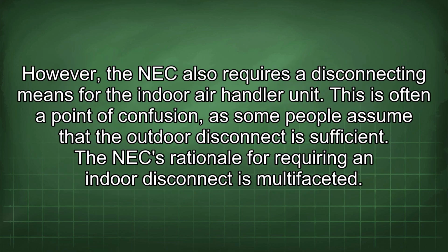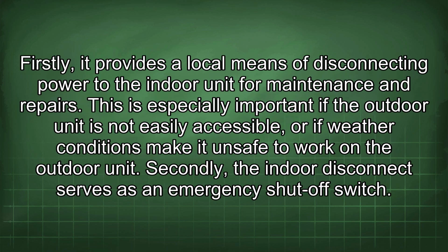However, the NEC also requires a disconnecting means for the indoor air handler unit. This is often a point of confusion, as some people assume that the outdoor disconnect is sufficient. The NEC rationale for requiring an indoor disconnect is multifaceted. Firstly, it provides a local means of disconnecting power to the indoor unit for maintenance and repairs. This is especially important if the outdoor unit is not easily accessible, or if weather conditions make it unsafe to work on the outdoor unit.